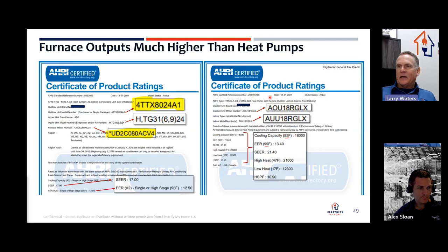Over here we have an inverter mini split system. This particular one I think is a ceiling cassette, I'm not sure. But I just happened to pull up this AHRI certificate. With this one we can achieve really high EER, really high SEER, have multiple heating stages, a really high HSPF rating, and we're doing it with 18,000 BTU. So the lack of performance we would get out of this system can easily be made up in an inverter system. So look at inverter equipment. It's a really good option to replace unitary, and it's less expensive.